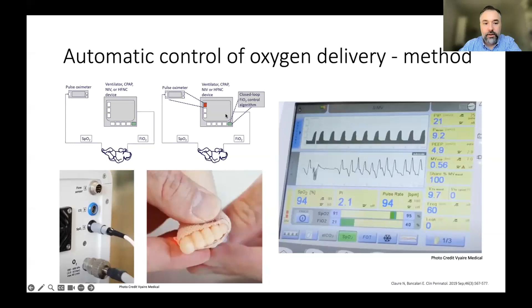Here we can see a clinical example of a patient that had desaturations. The saturation is in the upper panel, and on the lower panel you can see the FiO2. So when this baby was desaturating, the nurse would increase the FiO2. When the SpO2 went above the range, the FiO2 would be decreased, and again the saturation would be put back. So you can see it on the chart. And on the panel on the right, on the B, you can see that this patient was switched to the automated mode. So you can even see that the shape of this tracing is different. Obviously, the automated system will have a better response in terms of time. How it works clinically is another issue, but you can see that the shape of the tracing is different.